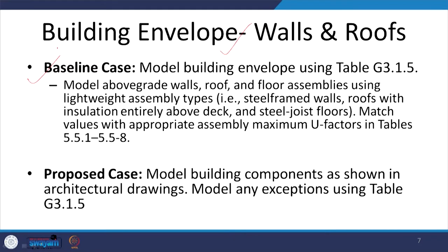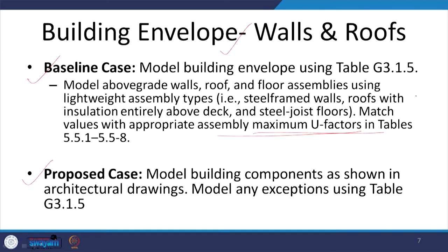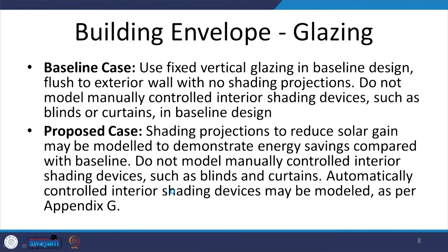When we are talking about the baseline method, the U factors, the U values, and SHGC of the building envelopes will be taken as given in the prescriptive requirement of the code. However, in the proposed case, we will use the building components and model them as per the architectural drawings and specifications. So, the maximum U values permitted will be the ones used in the base case. The proposed case may have higher or lower U values, as per the specification.